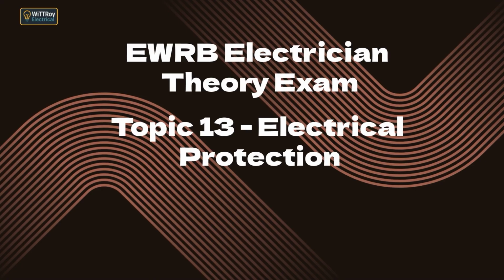13.1c: state forms of excess current protection: close excess current protection, coarse excess current protection. There are two forms of excess current protection, close and coarse. Close excess current protection is the more sensitive type. It will operate within 4 hours when the current reaches 1.5 times the designed load current of the circuit. This means the protective device responds sooner when the current is above normal levels. Close protection is found in modern protective devices such as MCBs and HRC fuses.